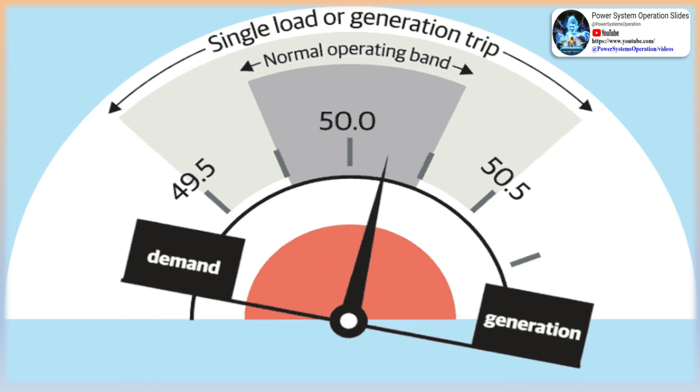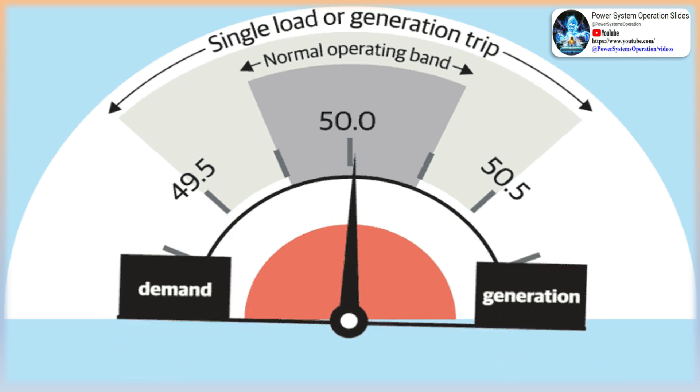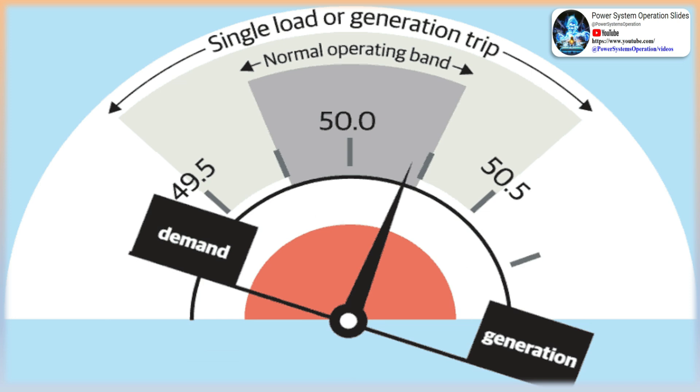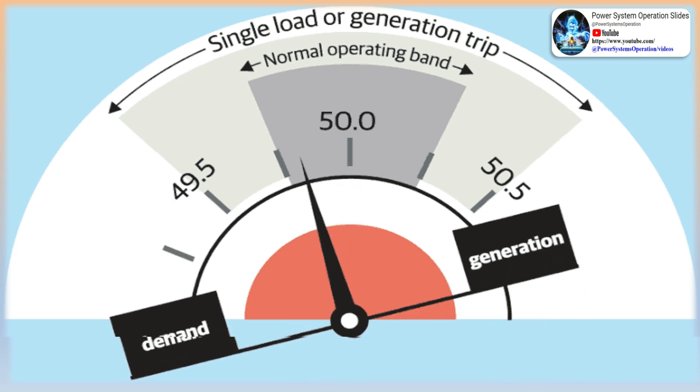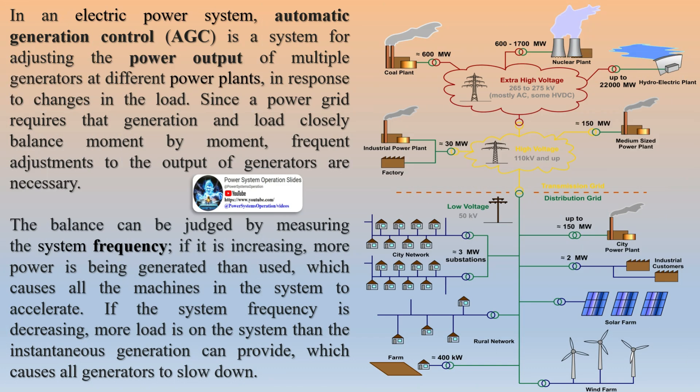The AGC will also automatically respond to system conditions and schedule changes with little manual input. The electrical system should be in a normal state for the AGC to function properly. The generation dispatcher is required to monitor the power system and have enough generation on bar to avoid a problem. AGC must only operate in Automatic Mode if the power system is stable and has AGC generation available and synchronized to the system. Let us discuss first AGC definitions.